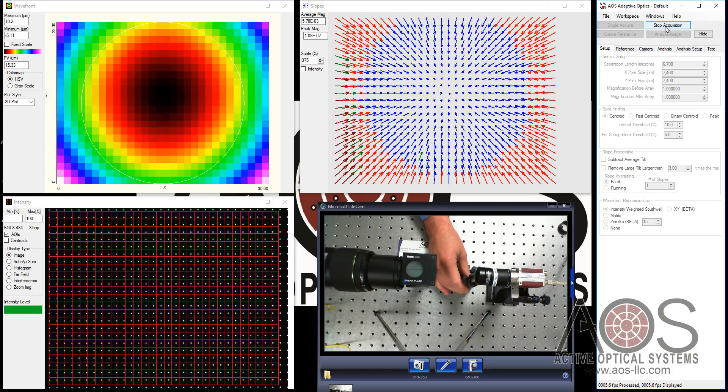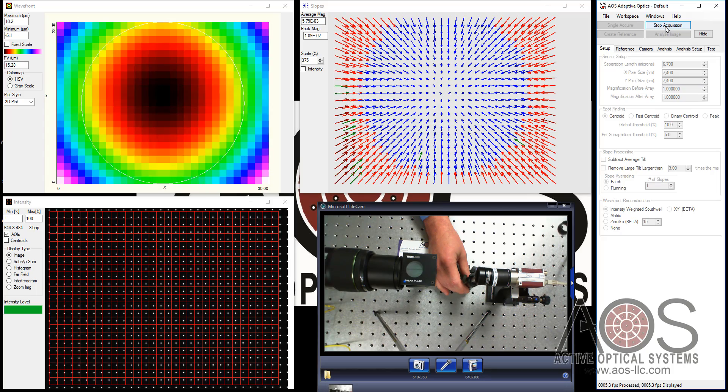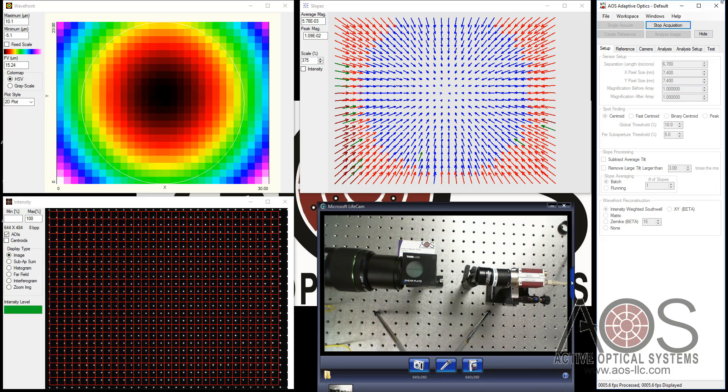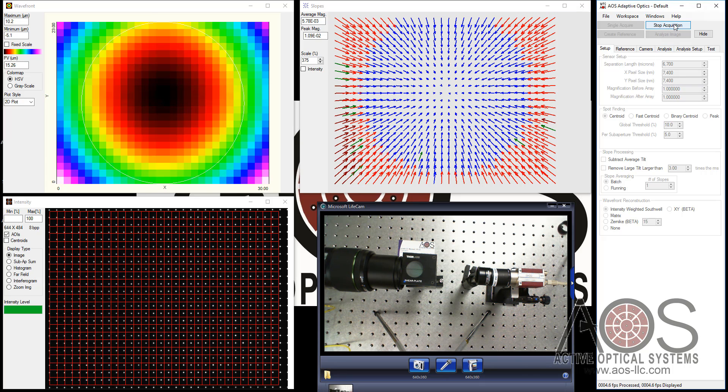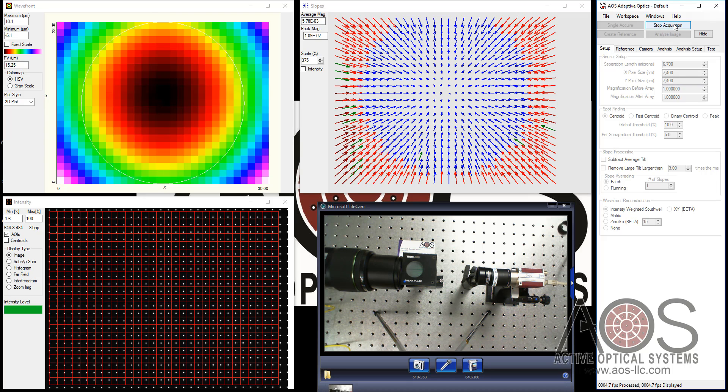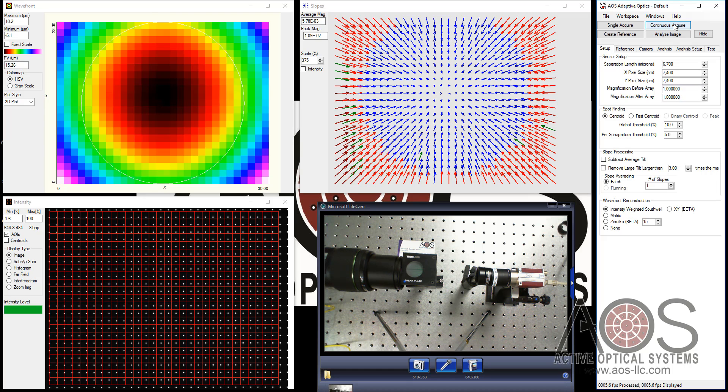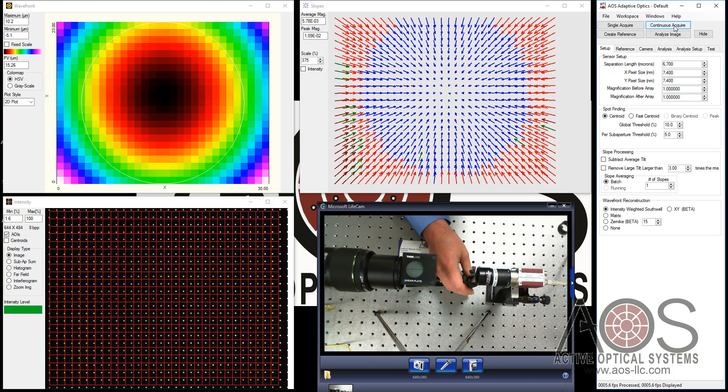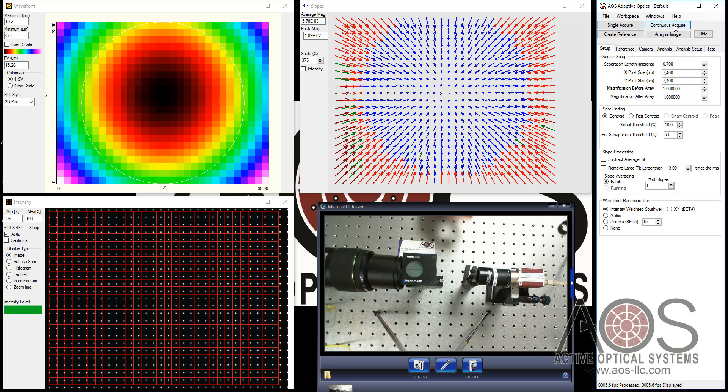Now I can slide this in and try to line it up in front of the wavefront sensor. I usually do that initially visually just to see if I got it lined up and then go through and see if I can center the wavefront curvature up. So that's nominally centered. It looks like I have a little height problem there, but it's not too bad. It's good enough at this point that I'm willing to stop this. Let me take a look at this lens. Actually, the lens I put in is a 300. So we'll take a look at the 300 first.